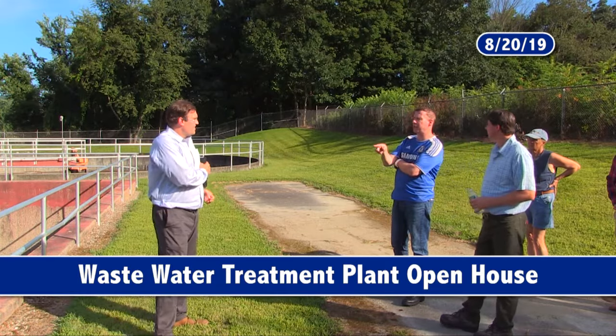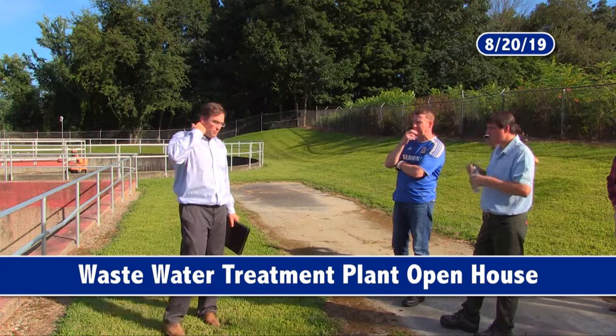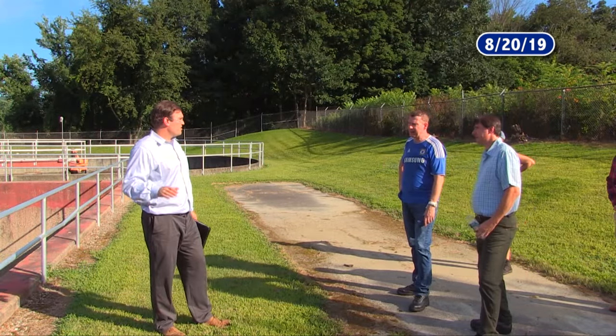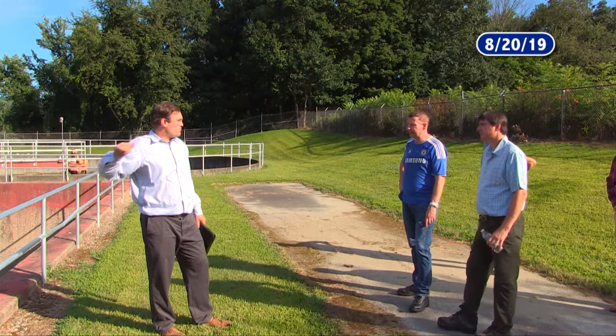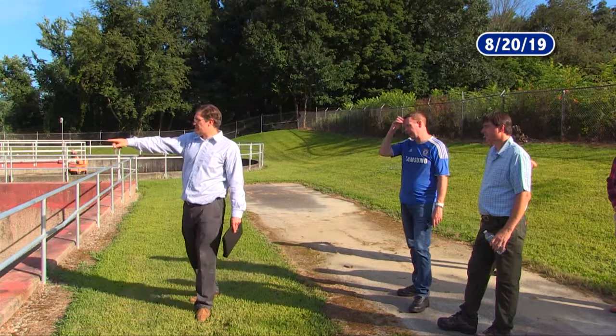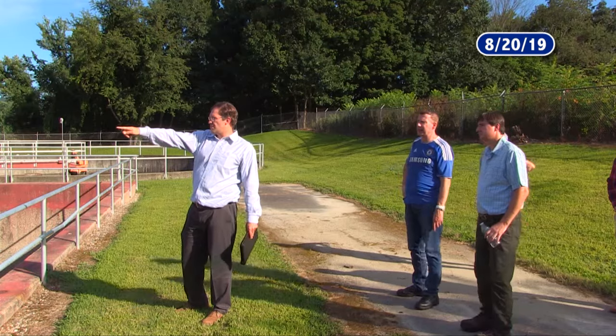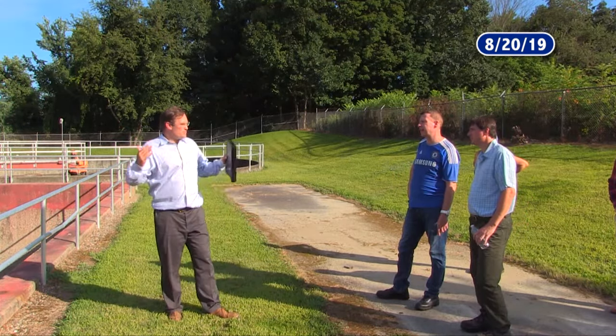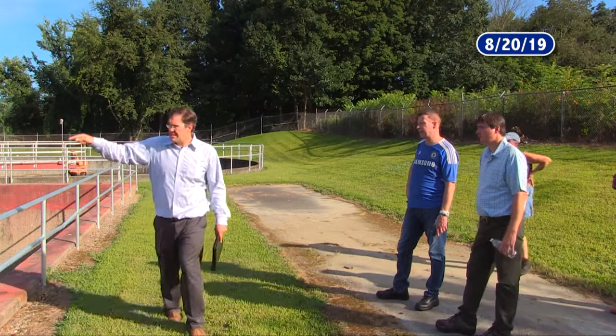And this concrete infrastructure you can actually use? Yes. So concrete tanks have a general life of 75 years if you do no maintenance on them. And with maintenance, because the tanks are generally full of water, it's at the water level where the maintenance needs to be done. Now you have some cracks, but those can be fixed with injections. And then if you look, most of your concrete at the top, you just chip out the bad concrete, you put new concrete in.